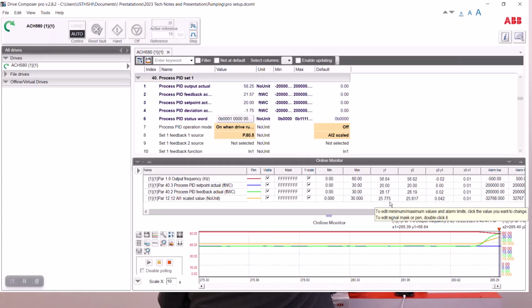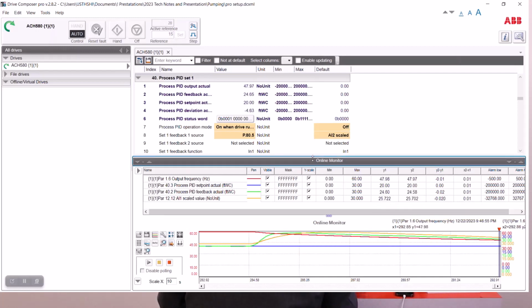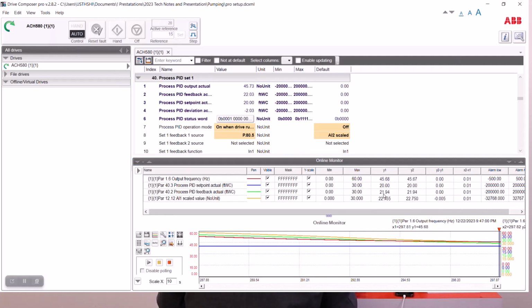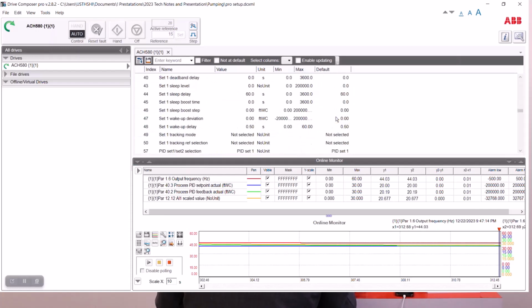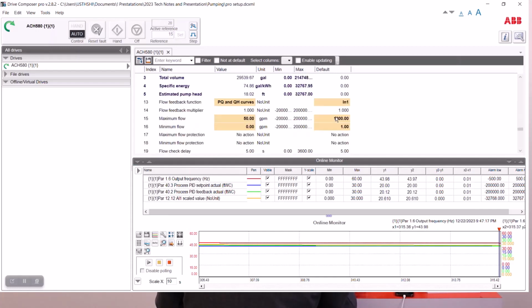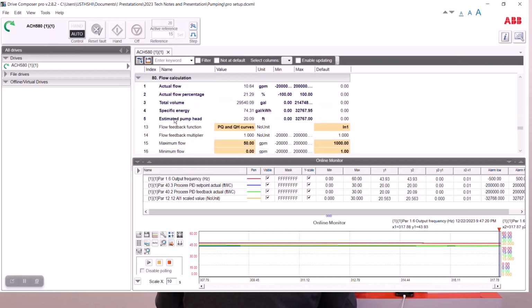And when I restrict the system, it changes its characteristics again. So here you are in Drive Composer Pro, looking at your graphs as I change the loading on the system, and how the system works its calculations to determine the head pressure that you want at the output of the pump. And it's doing this through sensorless pump control. This analog input is not connected to anything. My feedback source is parameter 80.05, and that is this parameter right here, estimated pump head, in the flow calculation section.